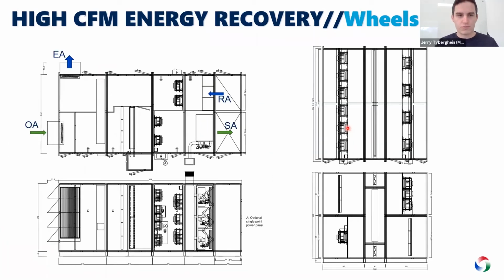Now, wheels, you probably are a little more familiar with wheels. These are energy recovery wheels. We can really stretch the capability of what's in a standard manufacturer's software. I would say standard manufacturers typically max out at about 15, maybe 20,000 CFM. We can take that up to about 35,000 on outdoor and 50,000 on indoor.